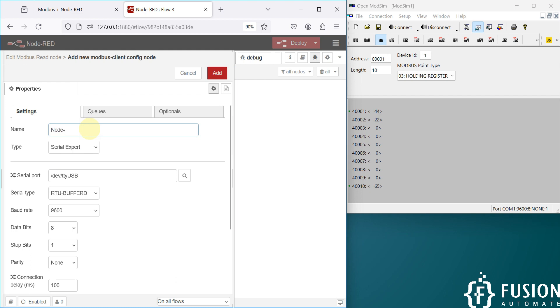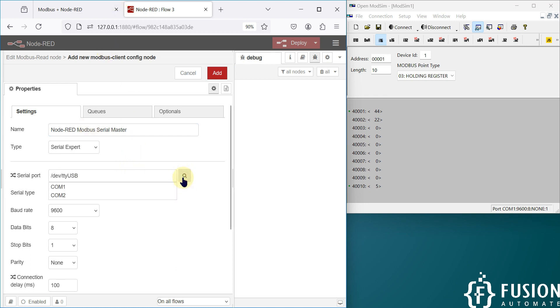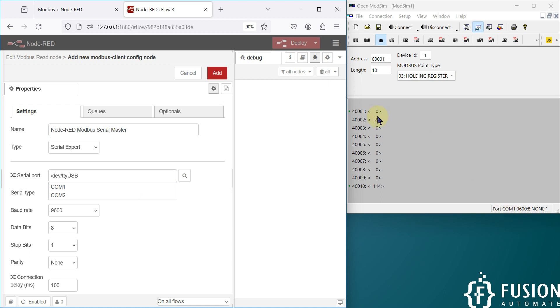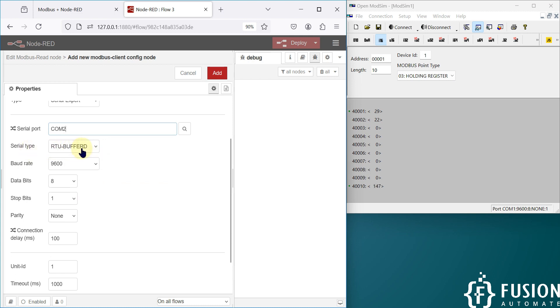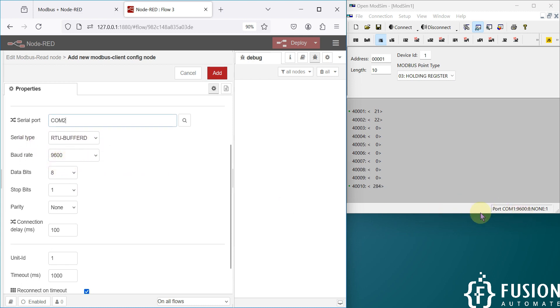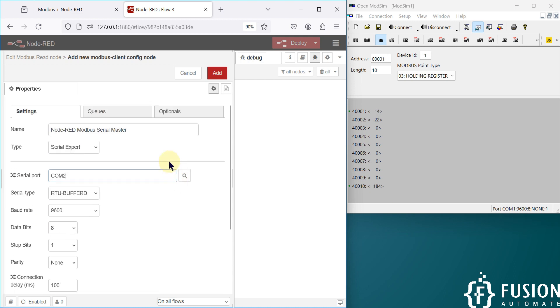This will be our Node-RED Modbus serial master. Then click Search to check the available COM ports. The simulator is running on COM1, and COM1 and COM2 are internally connected, so whatever data is available on COM1 will also be available on COM2. I'm going to select COM2 here. We will select serial type RTU buffer, baud rate 9600, data bits 8, stop bit 1, and parity none. That's it — the configuration for our Modbus serial master in Node-RED is done.